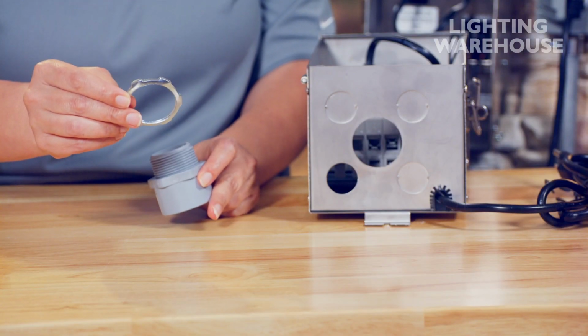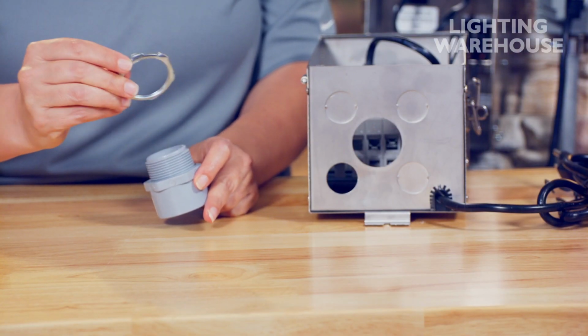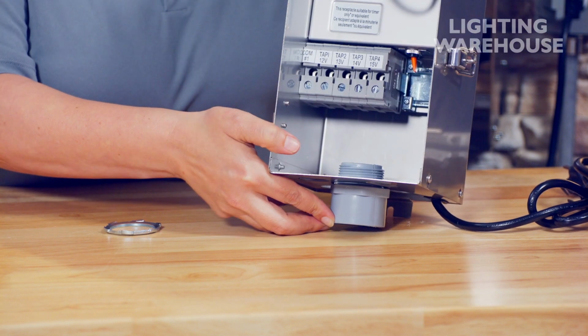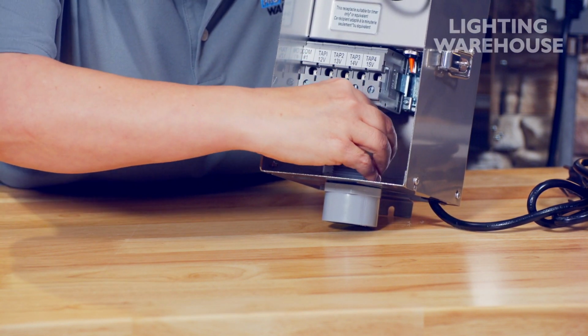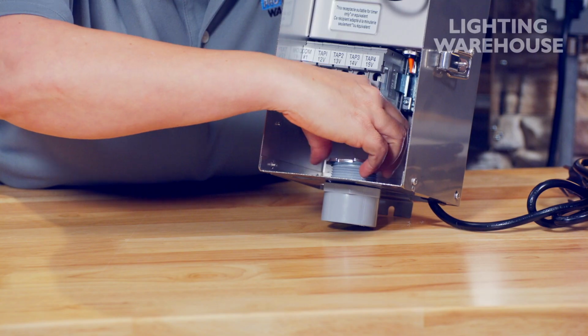Let's prep for the mounting. It's easiest to do this next part before mounting the transformer, and the transformer should definitely not be plugged in at this point. Start by punching out the knockout in the bottom for the cable access. Then you'll need a terminal adapter, which goes through the knockout and is secured by a lock nut. With that in place, you can mount the transformer at your chosen location.